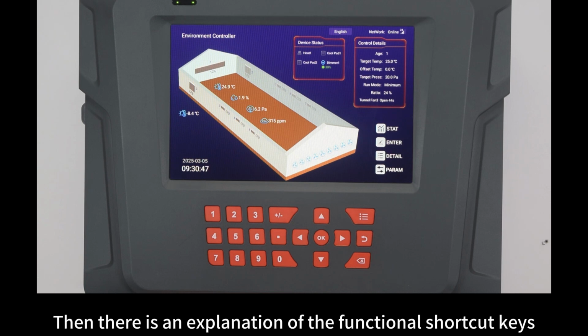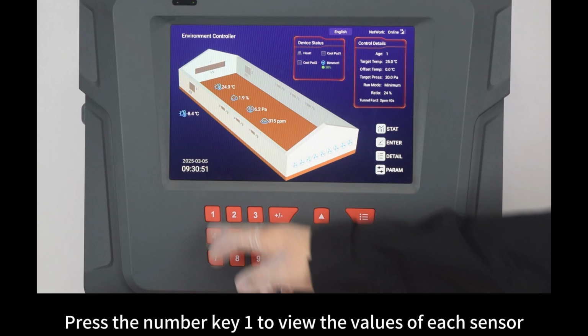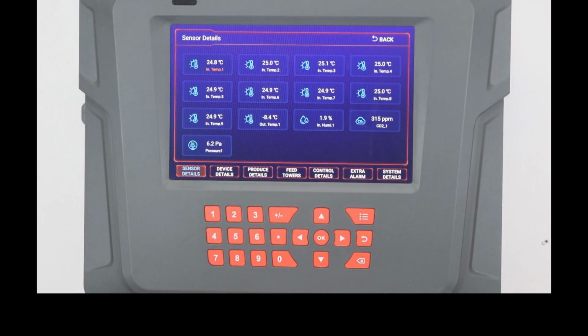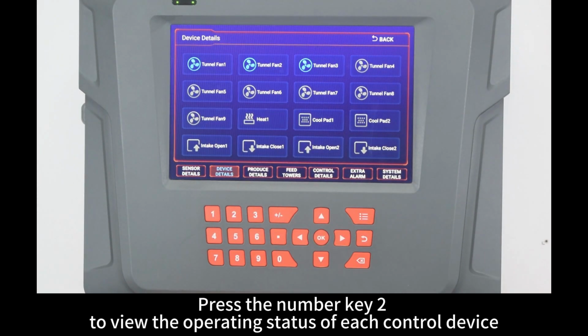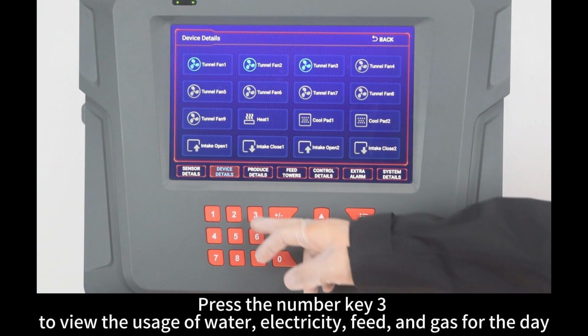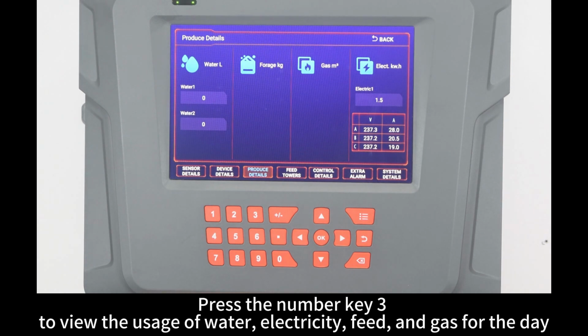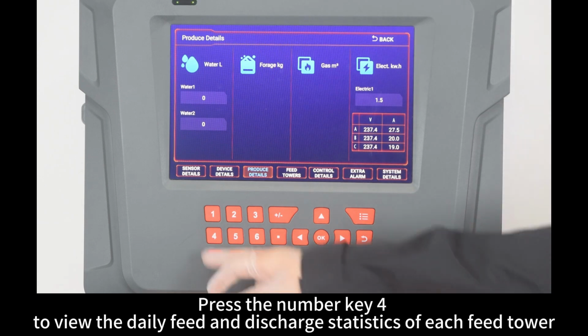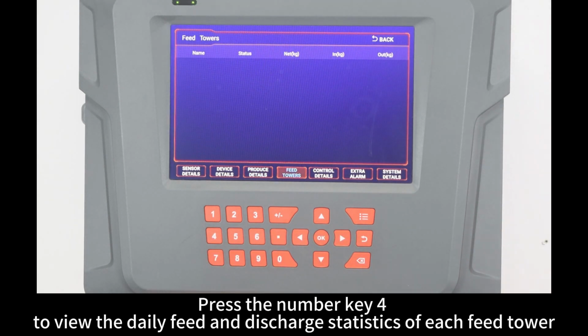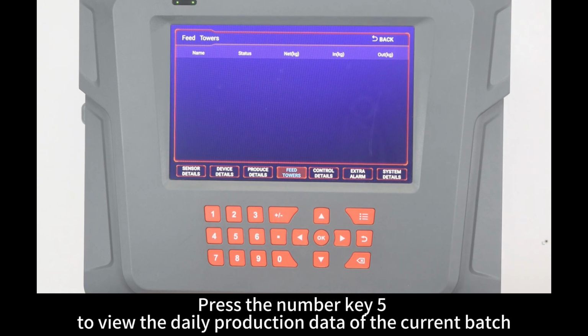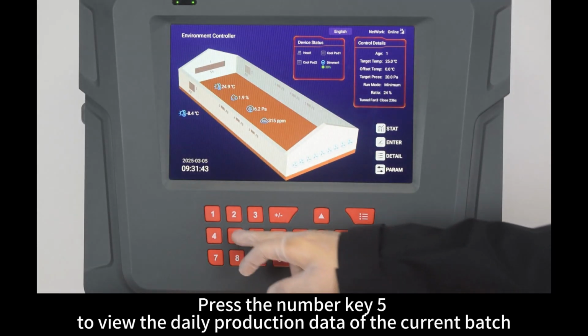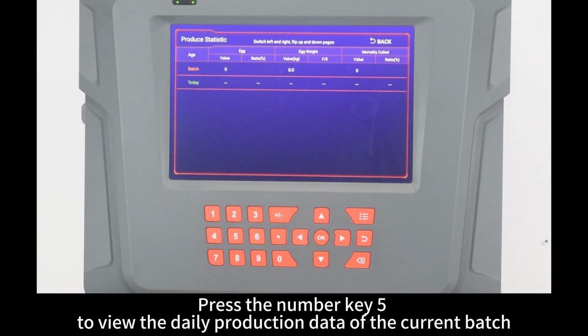Then there is an explanation of the functional shortcut keys. Press the number key 1 to view the values of each sensor. Press the number key 2 to view the operating status of each control device. Press the number key 3 to view the usage of water, electricity, feed, and gas for the day. Press the number key 4 to view the daily feed and discharge statistics of each feed tower. Press the number key 5 to view the daily production data of the current batch.